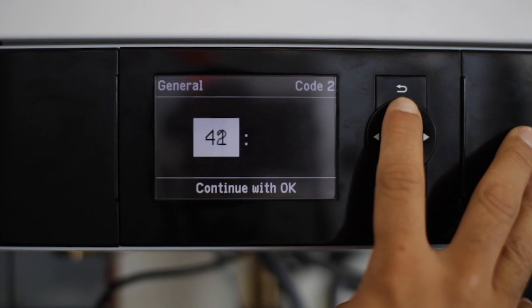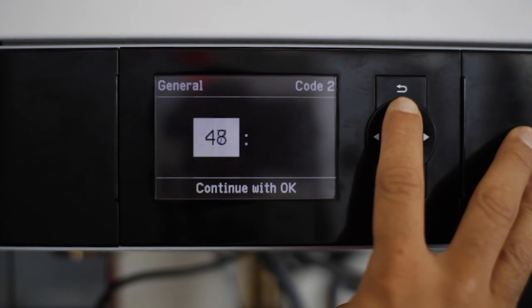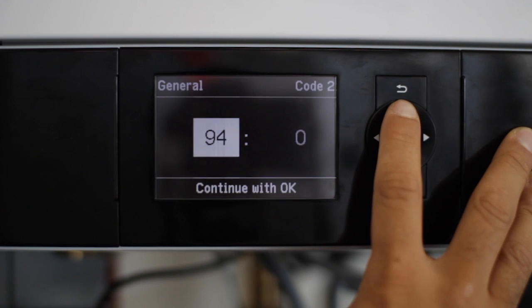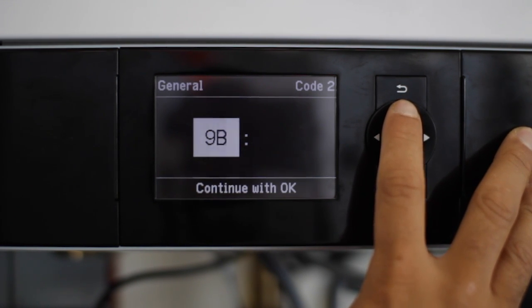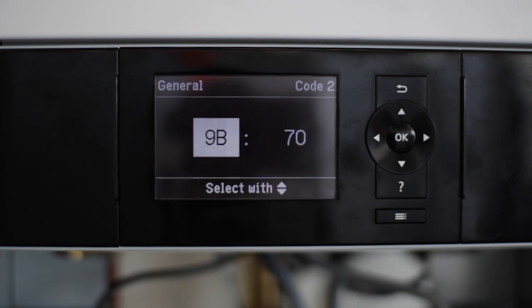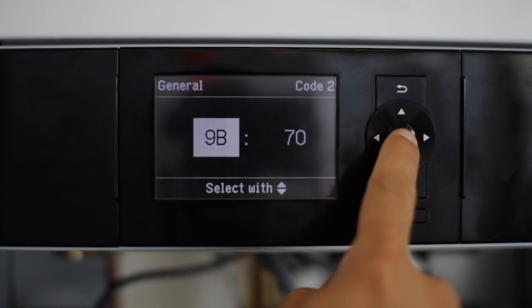The next address we're going to go to is 9B, 9 Bravo. This address pertains to the temperature you want the boiler to fire to once it receives an external demand. This value is always going to be in Celsius, so you might have to do a little bit of math to figure out what temperature you need if you're running Fahrenheit.